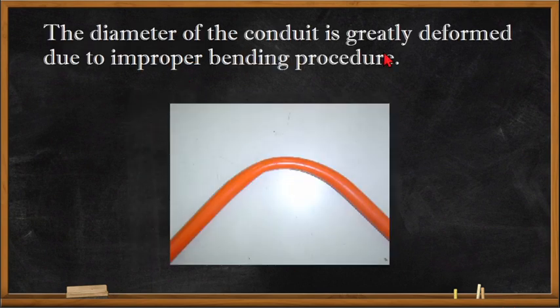Next, we have the diameter of the conduit being greatly deformed due to improper bending. In this type of bending, there is no kink, but the conduit has been deformed.